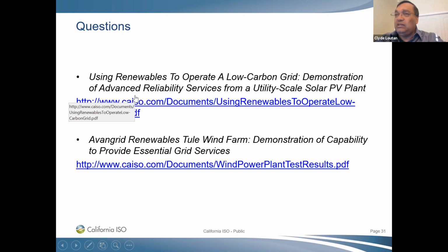In other words, if we see that we cannot arrest frequency for the two largest units, and there are two nuclear plants in the West, if we lose those units simultaneously and the technical study shows frequency dropping and approaching 59.5, then we're going to have to do something. That could be tuning wind plants or solar plants to respond in the inertia timeframe. We can look at things like fast load rejection on the system, which is similar to megawatt injection. There are a lot of things we can do to prevent tripping load unintentionally.